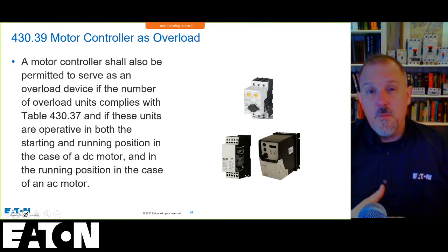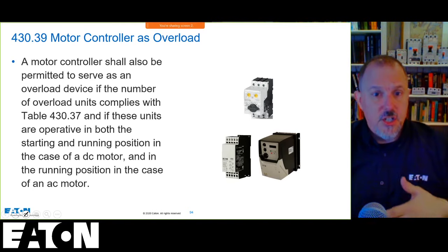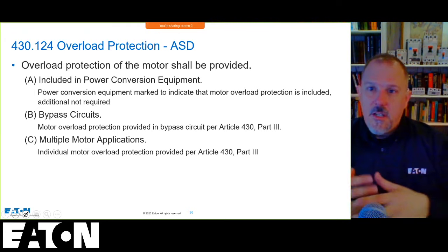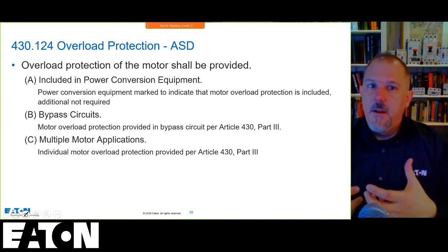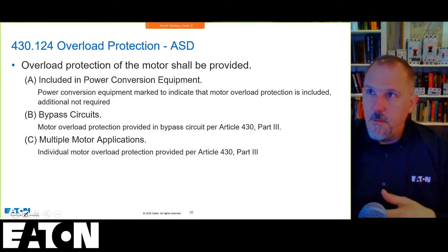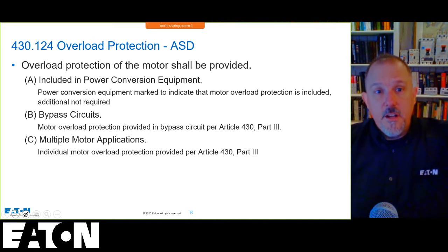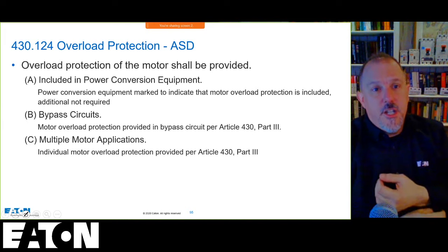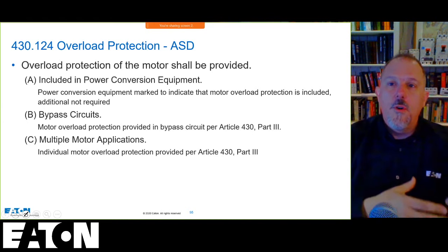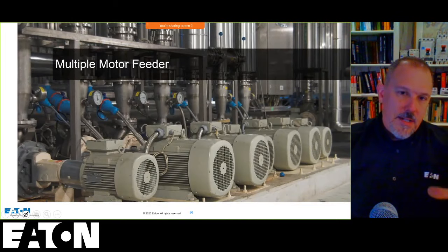And so for your smaller motors and things of that nature, they're going to integrate more of the protection with the overloads, with the controllers. And the only thing you have to worry about there is whether or not you're protecting for short circuit current ratings and things like that. Now, 430.124 talks about adjustable speed drives and, again, doing more inside of the equipment.